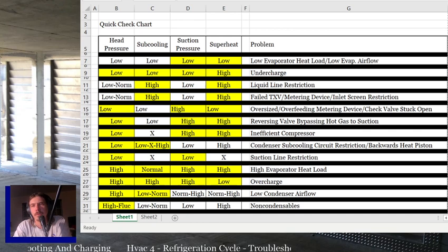And the ones that won't help you determine are probably going to be ones where you've got a couple problems together anyway. So in general, if the system's not removing very much heat, your compressor amps are probably going to be low. If the compressor's working hard and it's a hot day, your compressor amps are probably going to be high. If you've got low airflow through the condenser, your compressor amps are probably going to be high. Your discharge pressure should generally be the same as your head pressure anyway, unless you've got a problem in your condenser circuit.